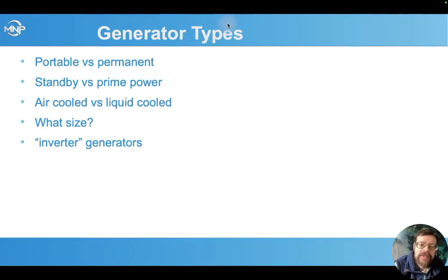Starting with generator types, we've got lots of different ways we can break them out into different types. Portable versus permanent pad-mounted generators is a big one. Generally, we don't recommend using portable generators with our inverter, and this is for a couple of reasons. One is just the size of these generators. Really, you want a 12 to 15 kilowatt generator minimum to work well with this inverter, and we'll go over why that is when we talk about sizing generators. But there's not a lot of the portable ones that are that large.